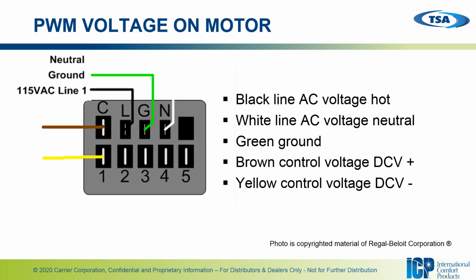And here we show a diagram of the connections at the motor. Your black line is going to be your AC voltage hot, your white line is going to be AC voltage neutral, and green is going to be a ground. Then you've got your yellow going to your speed tap on your motor, and your brown coming into the common. Make a note that your common actually comes in on the high voltage connector on these motors.